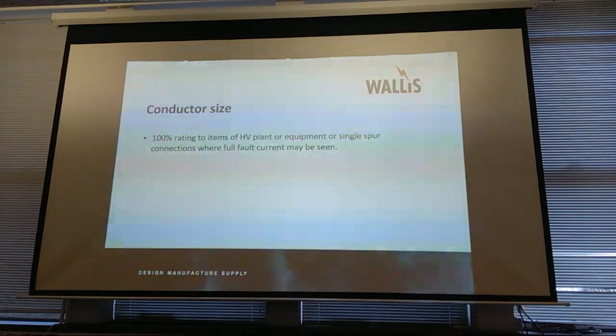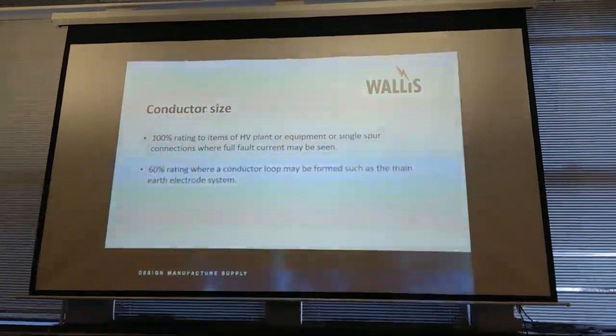So if you do lose one, or somebody comes along trying to fill his Christmas box up with a bit of copper, then you've still got a secondary connection. And again, 60% of the rating where a conductor loop may be formed, such as part of the main earth system. So when you've got a ring around the substation, you've got 2 diverse paths.